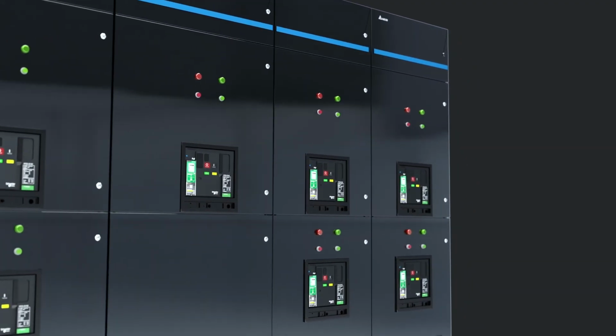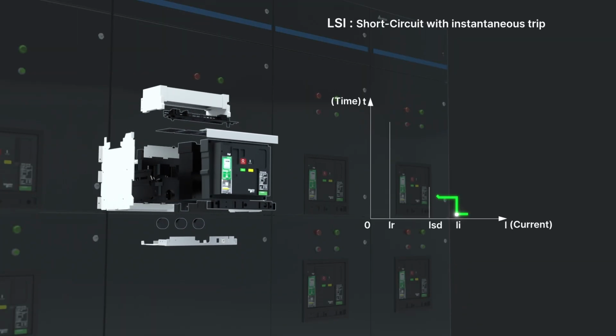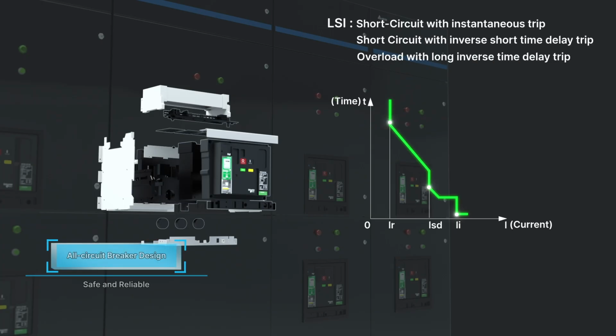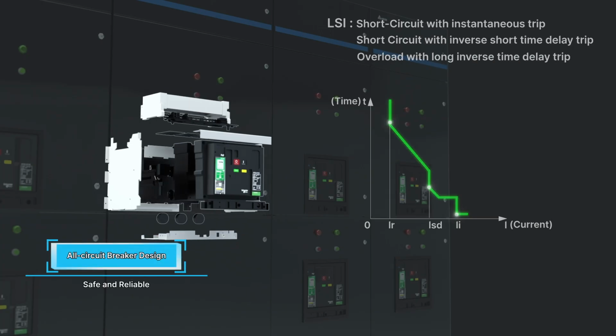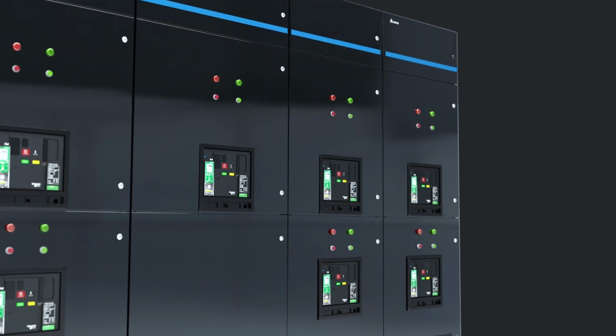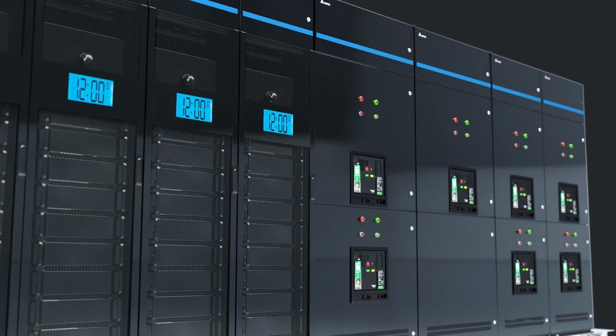With the high-performance circuit breaker switch design, we achieve short-circuit instantaneous, short-circuit time delay, and overload long-time delay protection through parameter settings. This design is more convenient and reliable for daily data center operations.